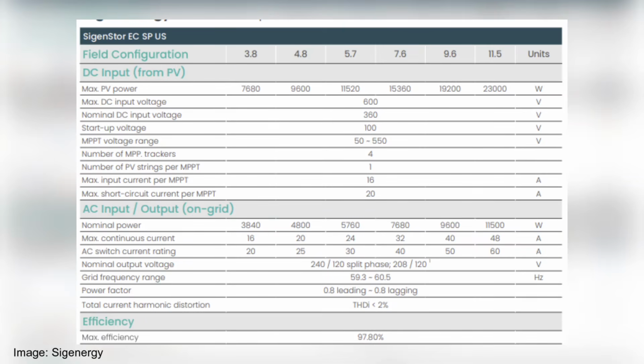This is the inverter. This unit actually ships as one singular unit and is configured in the field depending on the size of installation that you need. So it can go anywhere from 3.8 kilowatts on the low end all the way up to 11.5 on the upper end. It's also capable of hitting 200% oversizing. So on that 11.5 version, it can actually accept up to 23 kilowatts in of PV DC solar. The unit has 4 MPPTs, so you're able to design on complex roof planes with different angles all into the one single unit, which gives a lot of flexibility to installers and homeowners if your roof isn't just one single south-facing plane. The unit also has a maximum efficiency at 97.8%, which puts it in the top tier of inverters in this category.